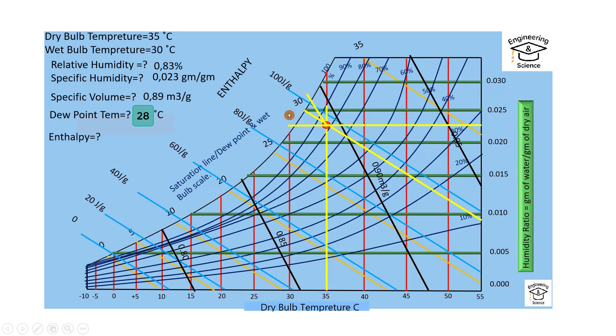Regarding enthalpy, the white-blue lines represent enthalpy. We draw a line parallel to the enthalpy lines, and it is located between 100 joules per gram and 80 joules per gram — so it is about 96 joules per gram. That is the full solution for using the psychrometric chart. I hope it can be helpful — have a nice time!